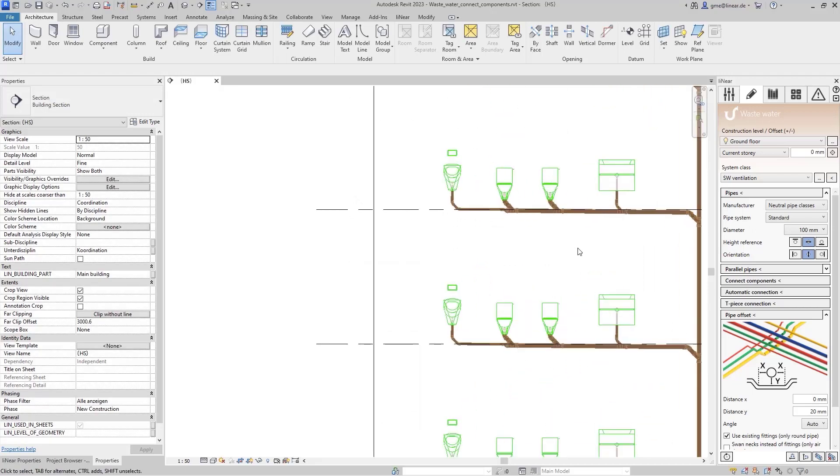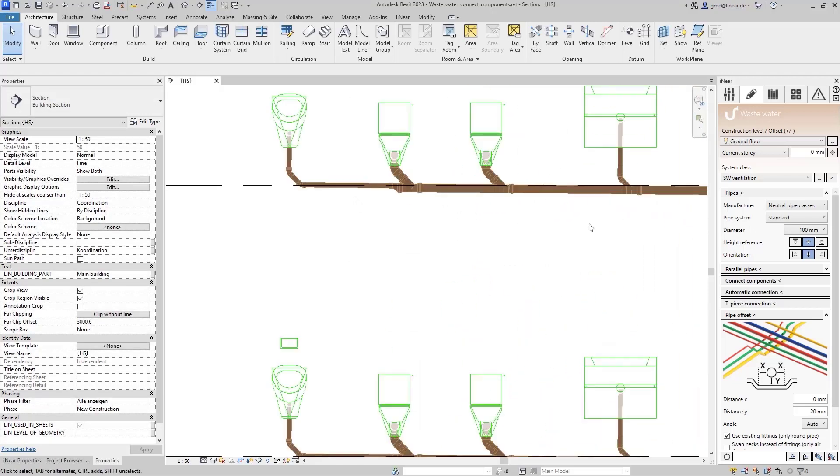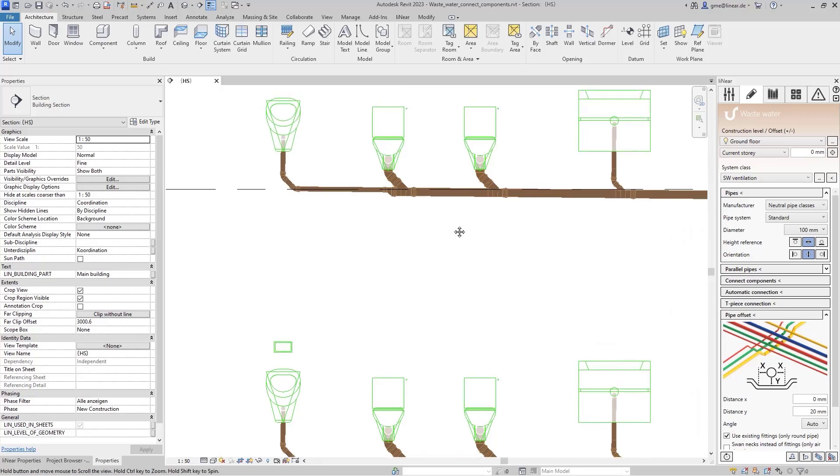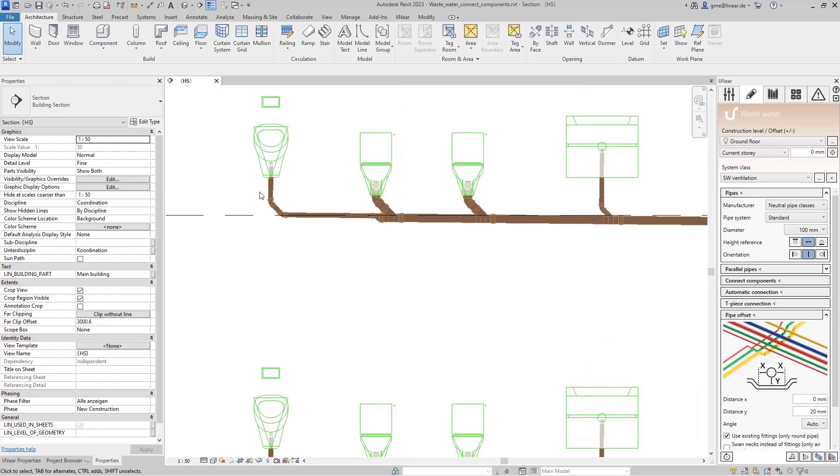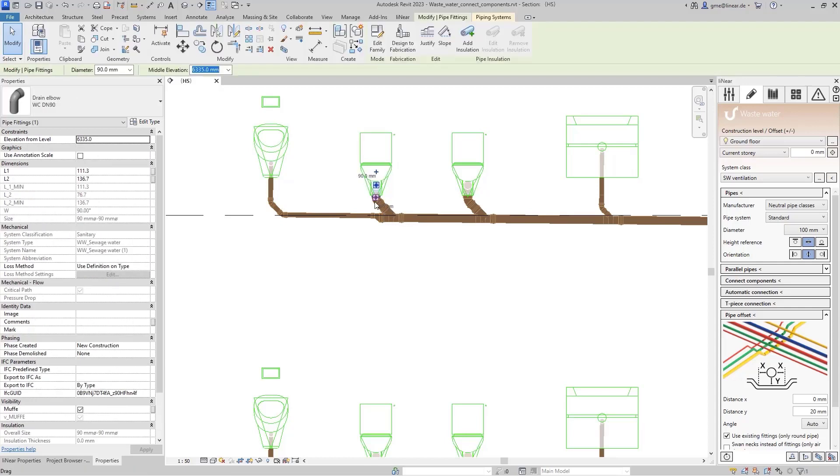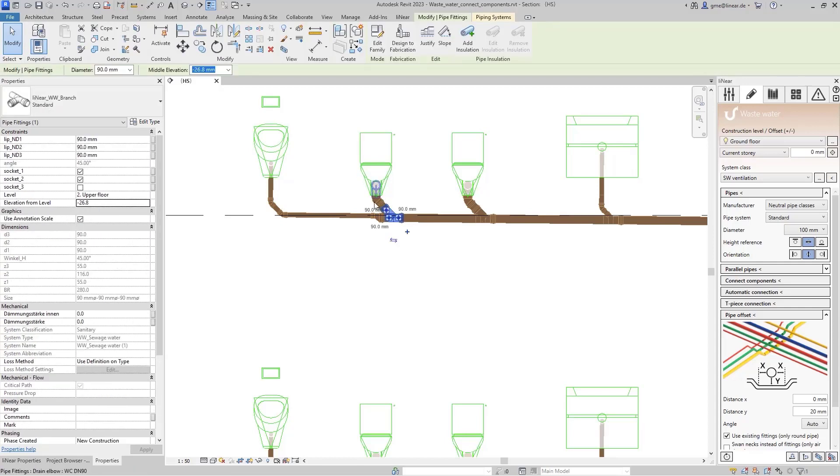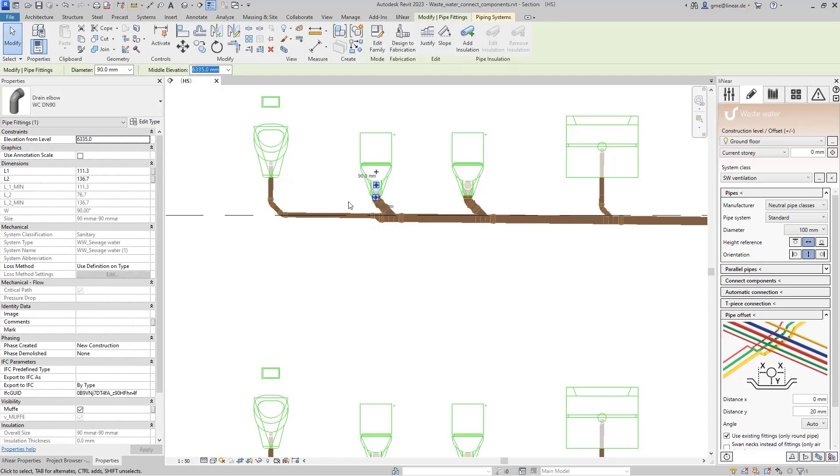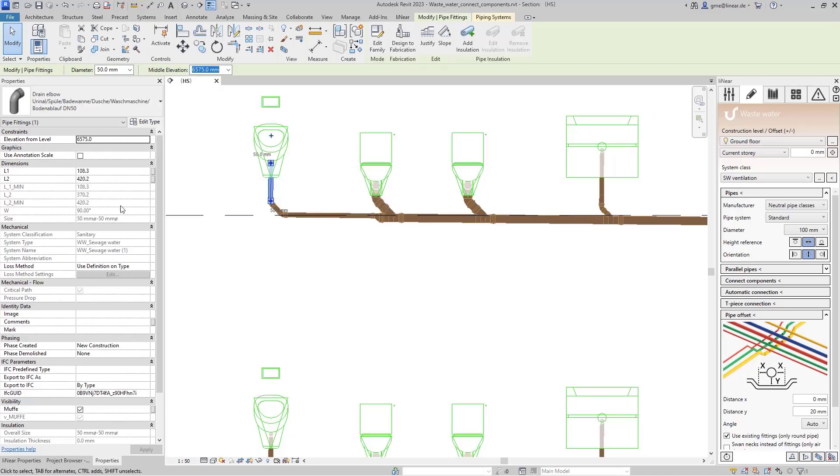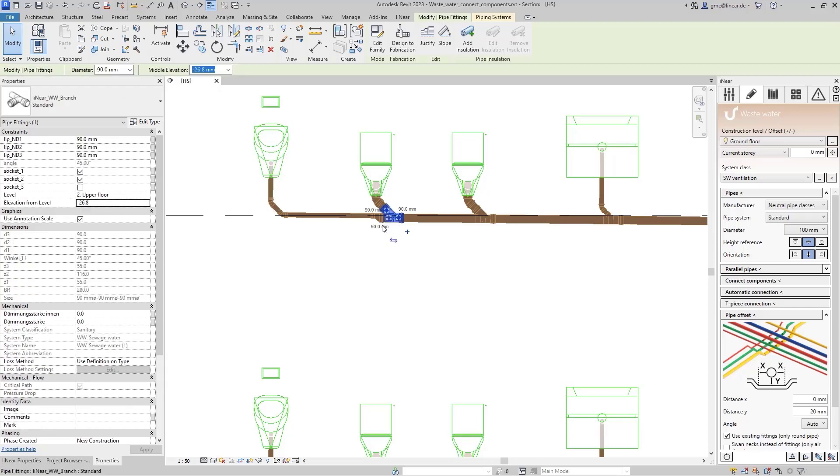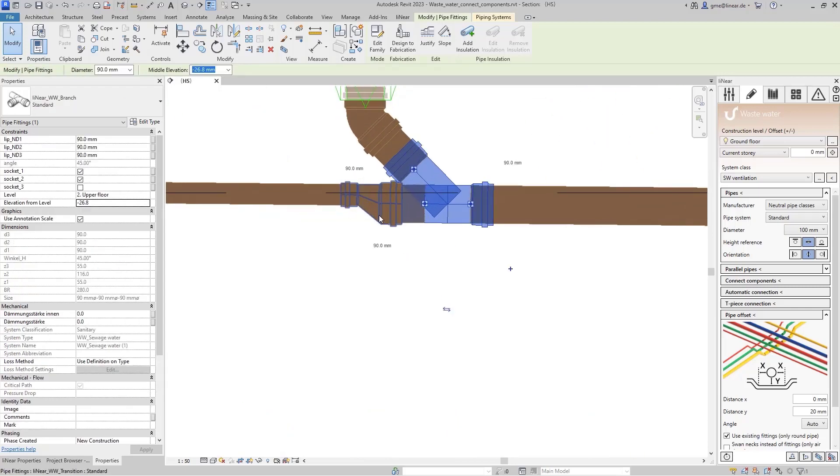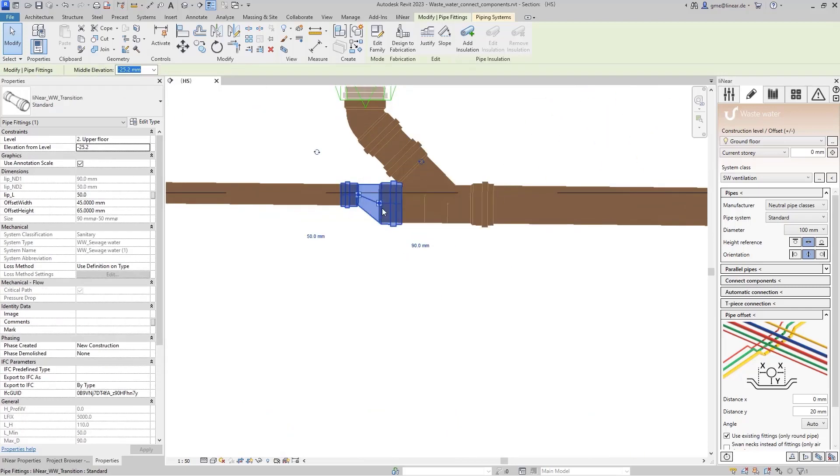Now all objects are connected and we can take a closer look at the results. As you can see, the components were connected according to their requirements, and the toilets were connected with a pipe in diameter DN 90 using a branch. For the urinal and washbasin, smaller diameters were used and suitable branches and an elbow were integrated into the pipe network.